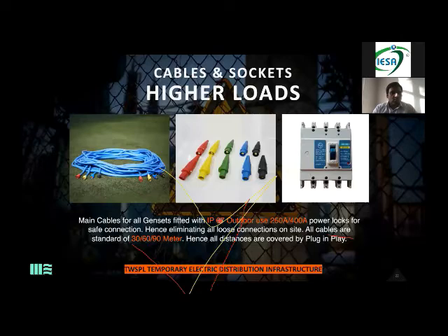Your gensets are outside. You may be in an exhibition hall where the cables are inside, but when you're doing an outdoor event, 90% of the time your gensets are outside, obviously. When you're laying cables, maybe it rains. Our venues are not so nicely done. Water logging is a very big problem. When you are using these power locks, even if they are submerged in water for half an hour, or when it starts raining, there is no problem.